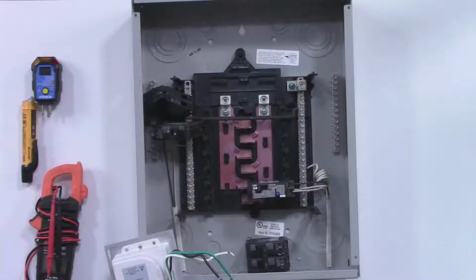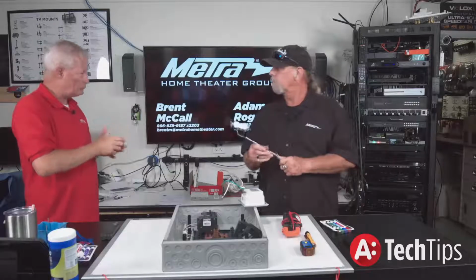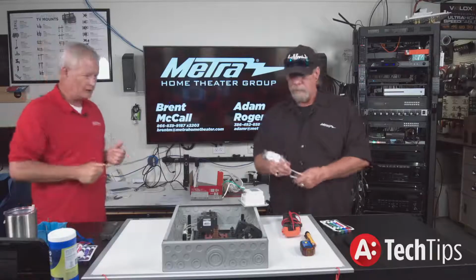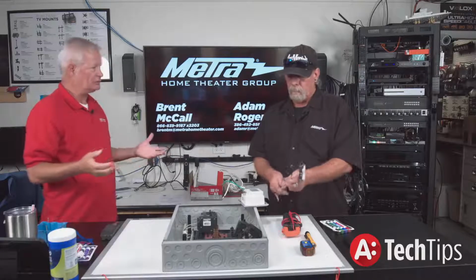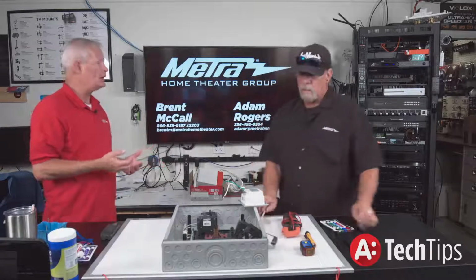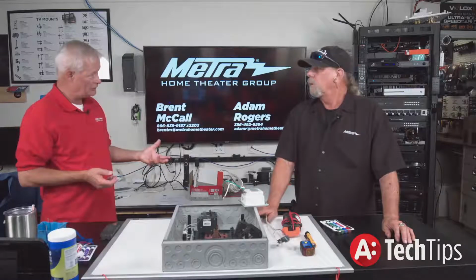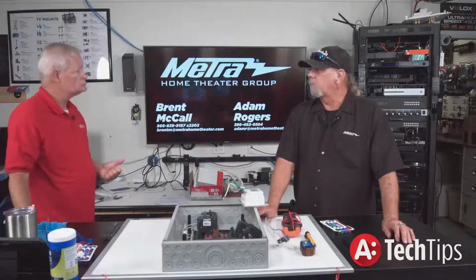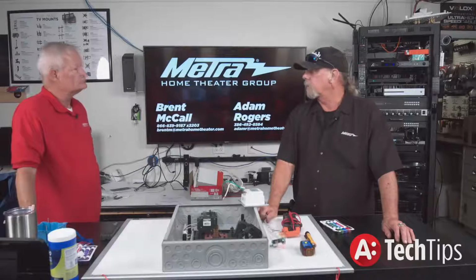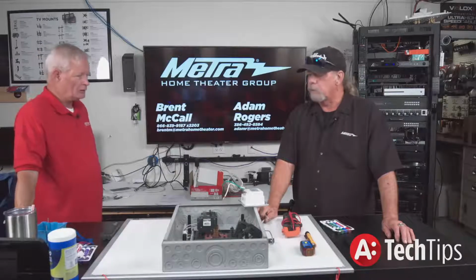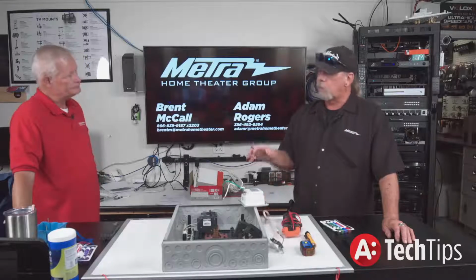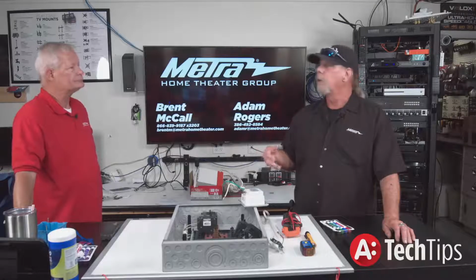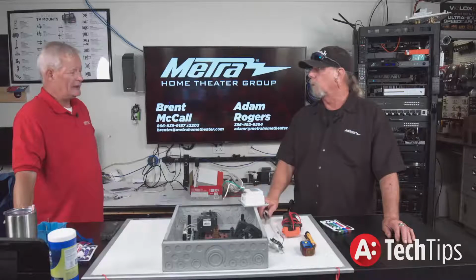Now, the different colors or gauge sizes on the wire nuts? Yes. Typically I generally see orange out there unless it's 3 or more, or 12 gauge—in that case it goes to yellow. We generally use yellow on 14 and 12 gauge wires, and even 10 gauge wires now too. Wire nuts are all listed for how many wires you can put underneath them—it's all listed on the box.